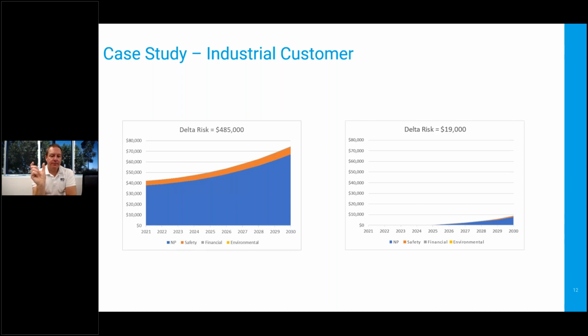What you're doing when inspecting assets more regularly is shifting the failure mode. So failure mode 1 is minor, failure mode 2 is serious, and failure mode 3 is major. Major means an explosion, secondary damage, a big cleanup, and a longer repair. Failure mode 2 is an unplanned outage where the protection operates correctly and the asset doesn't explode, but you do have to perform a repair. Failure mode 1 is just inspections and minor repair works.